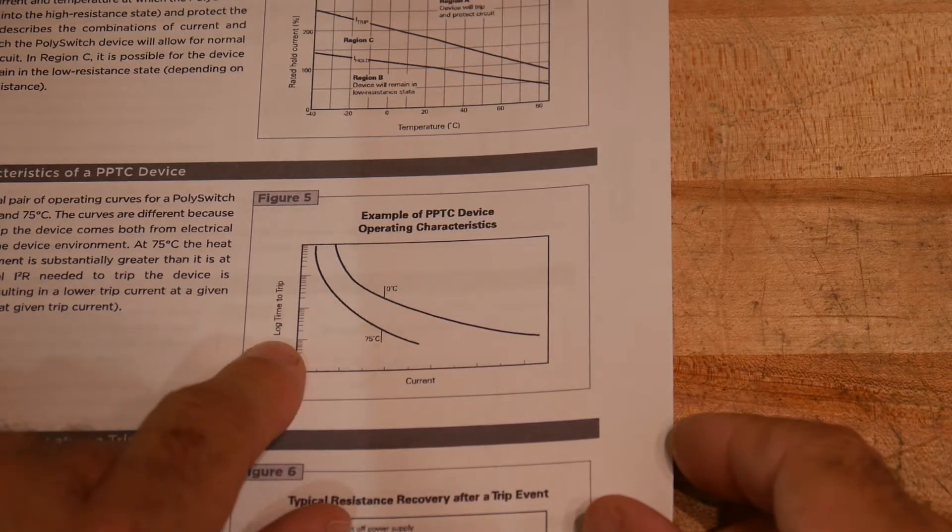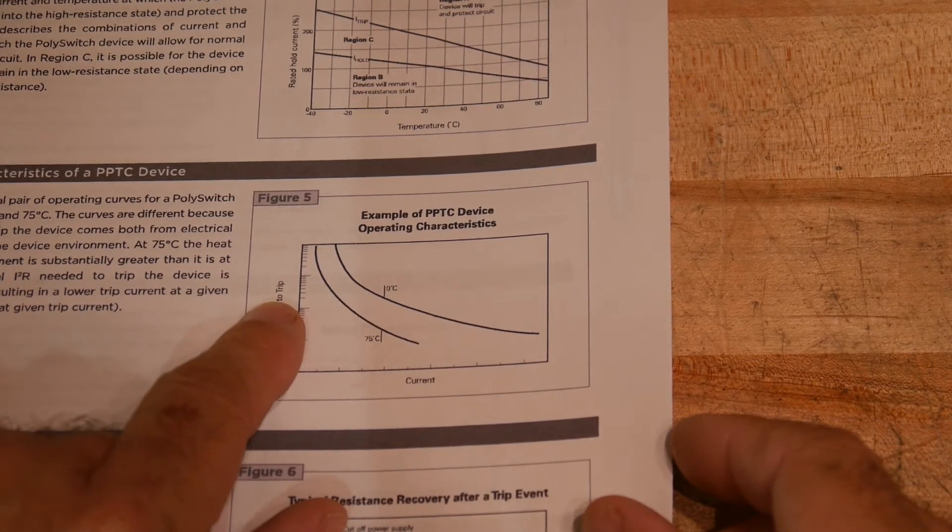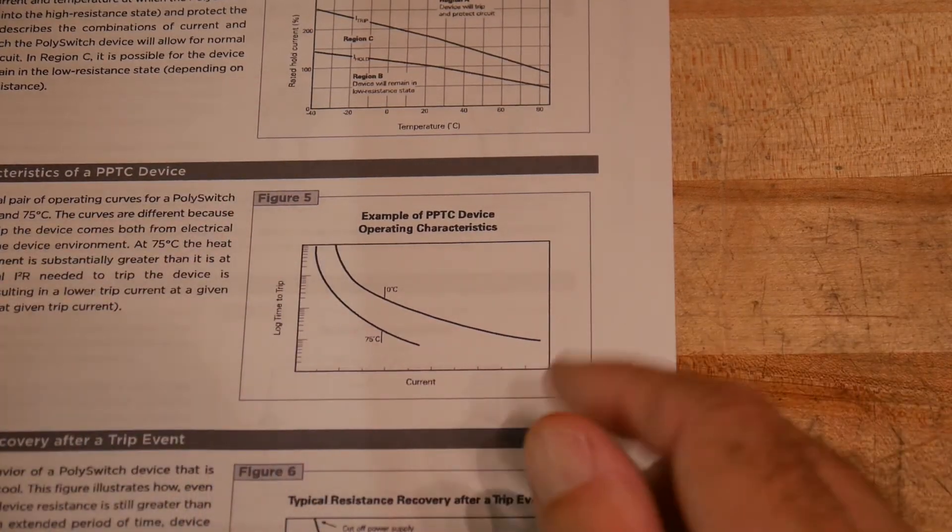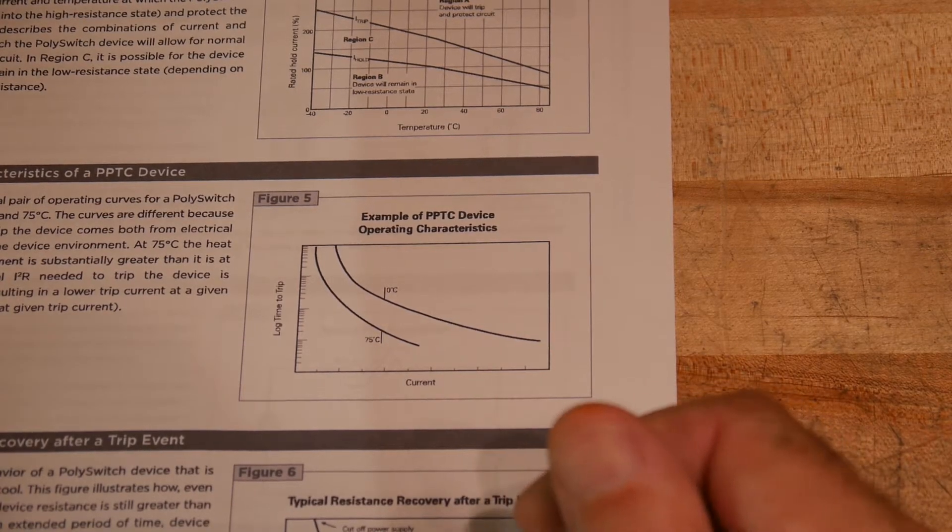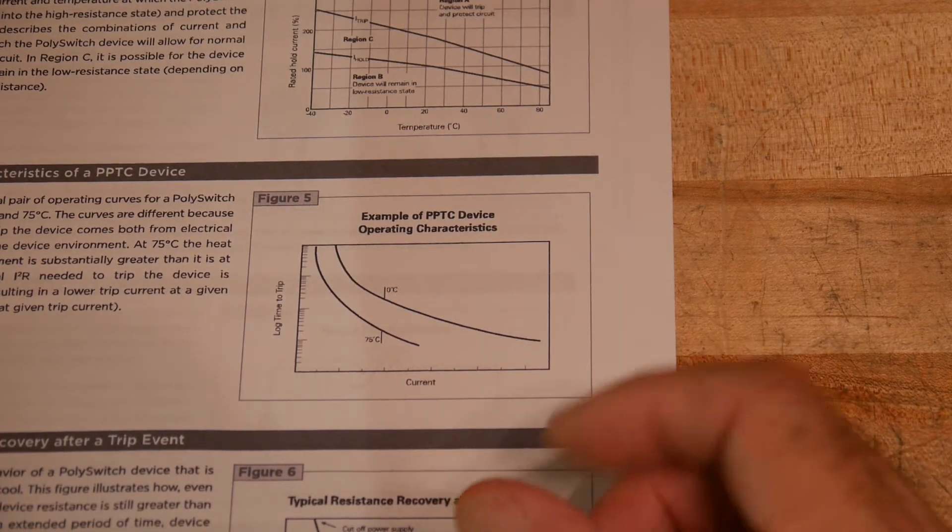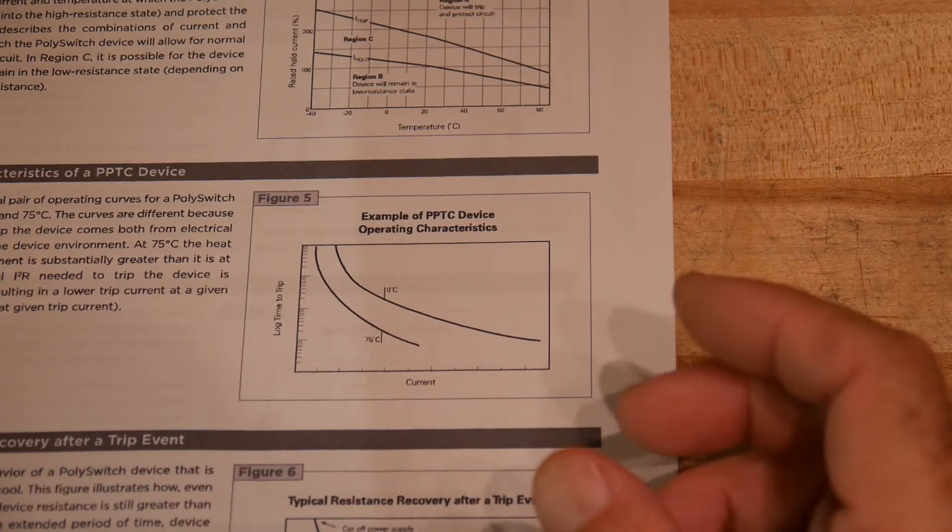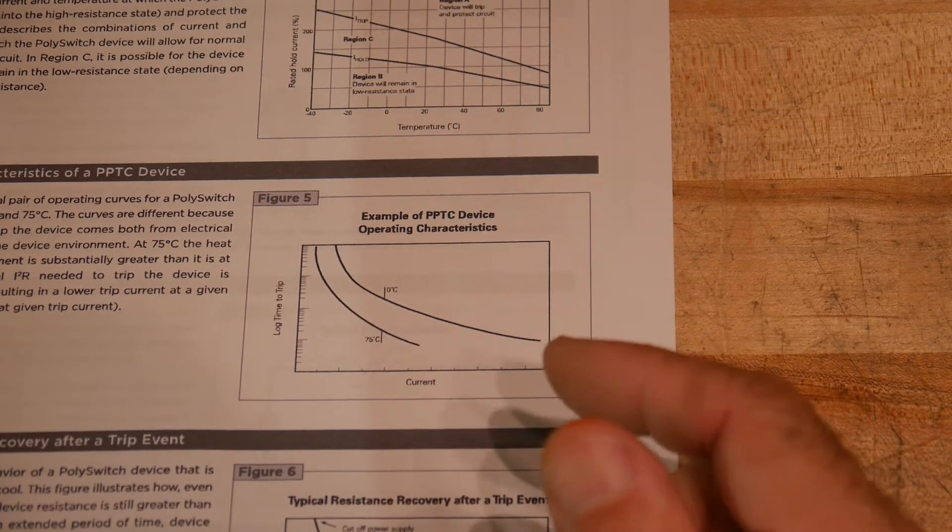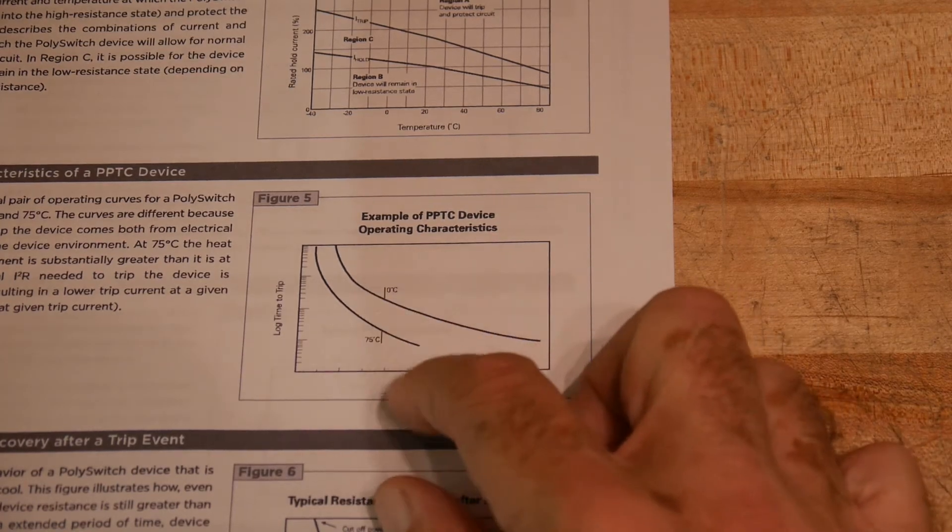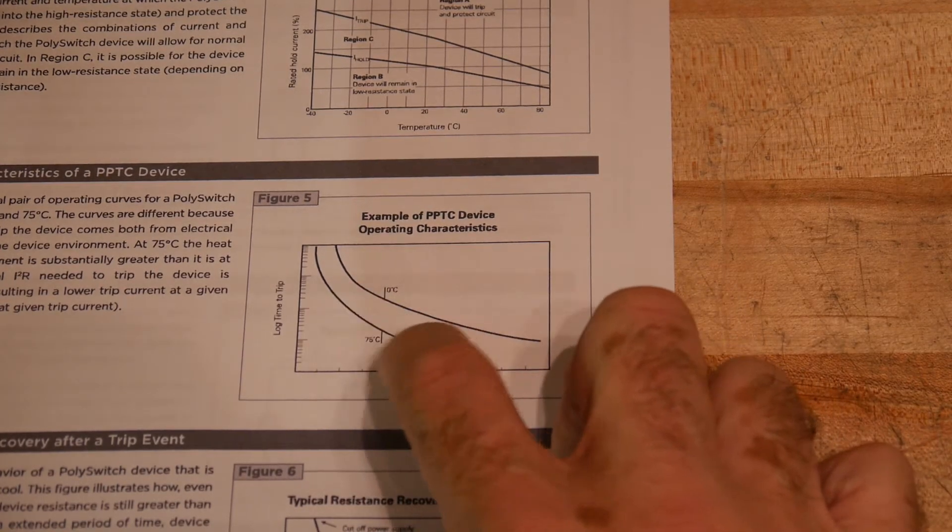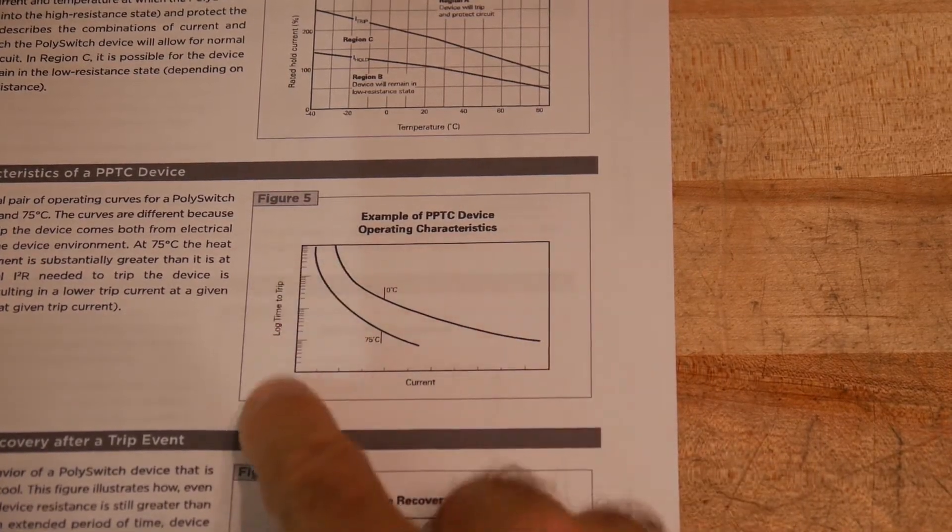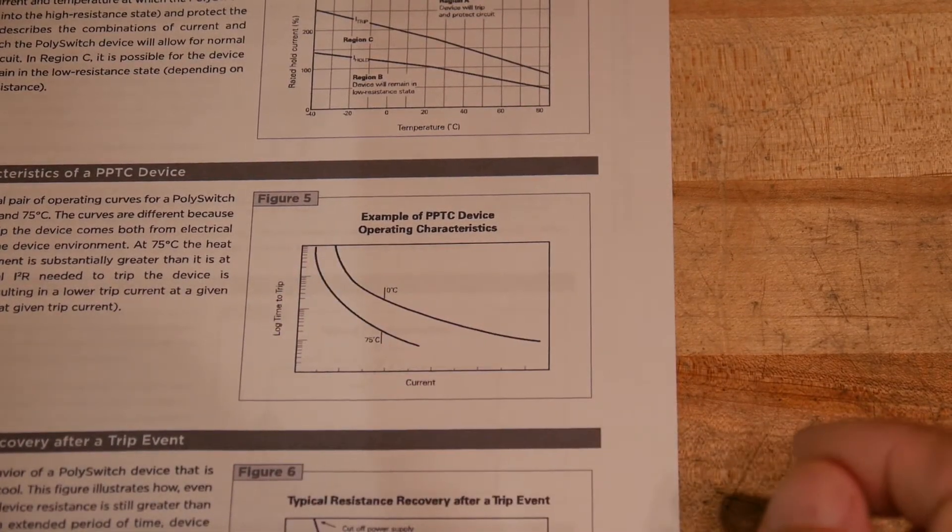Let's see. This is log time to trip. So this is the amount of time it takes to trip and the current. And we saw that when we were testing it, that when we were just a little bit over the trip point, it did take a long time for that power to build up, the energy to build up, and it finally tripped. Whereas if you were quite a ways over it, then the time was much quicker. So it turns out that it follows this graph. This is a log graph as well.